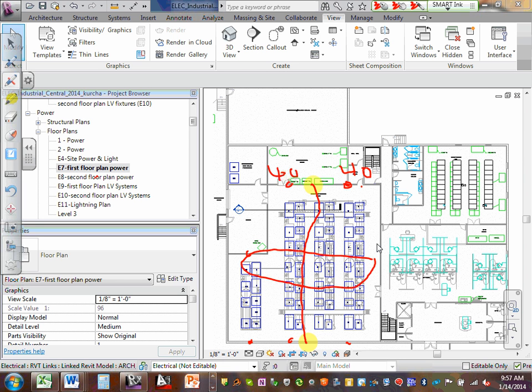Okay, so I'm looking at this now. Let's go on the perpendicular axis. Okay, 60 feet: 30 feet to this side, 30 feet to that side. Got it, a total of 60 feet. So you can't be any more than 30 feet from the outside wall to your first device. Gotcha. Now, you can go from this device at 30 feet from the inside wall. You can go 60 feet to the next device.